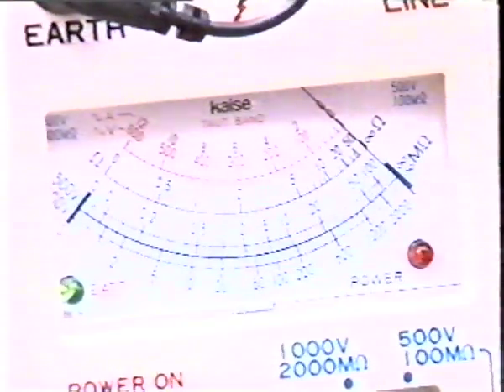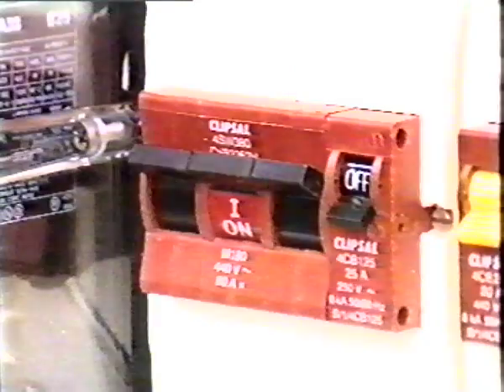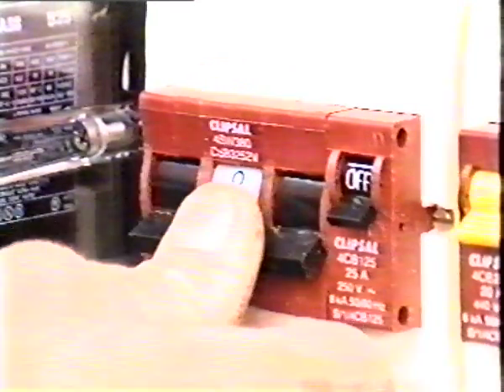The testing is done with an ohm meter as follows. Between the live conductors of each individual single-phase or multi-phase circuit, with supply disconnected, usually by opening a circuit breaker, RCD or fuse, with switches in the circuit on, and with portable appliances disconnected from socket outlets. This demonstration shows the use of an ohm meter connected between active and neutral conductors at the origin of a final subcircuit. This test is similar to and can be performed in conjunction with Test D, which dealt with the transposition of neutral and earthing conductors.